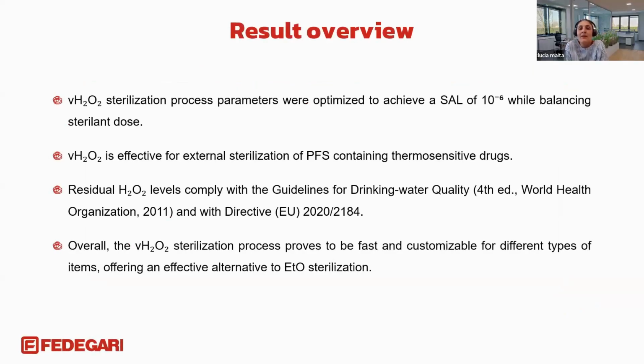So, to summarize this case study, the sterilization process was successfully optimized to achieve the required sterility assurance level, and H2O2 proved to be a suitable approach for the external sterilization of the syringe containing a thermosensitive drug. The residual amount of hydrogen peroxide remains within accepted limits based on the applied analytical methods. Overall, the results confirmed that H2O2 sterilization can represent an alternative to ethylene oxide, especially for heat-sensitive products where the traditional methods are not applicable. As always, the final process selection should be based on case-by-case assessment, including the product characteristics, the packaging configuration, and the regulatory expectations.